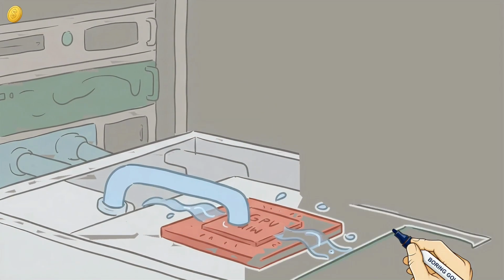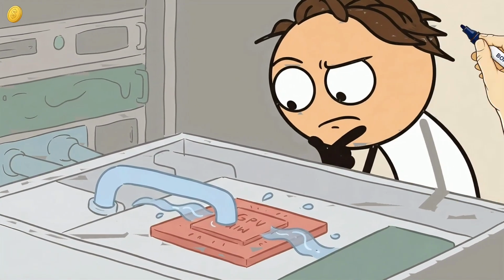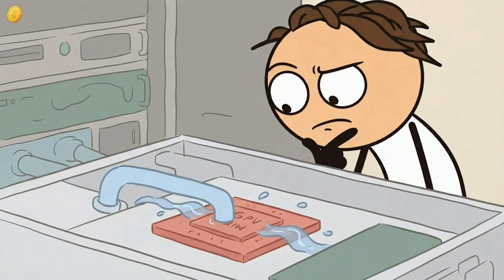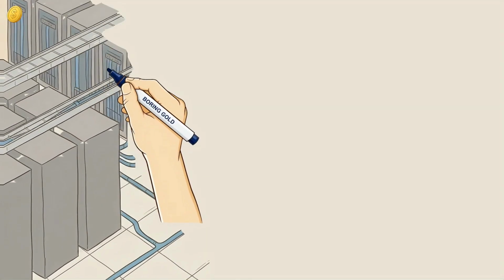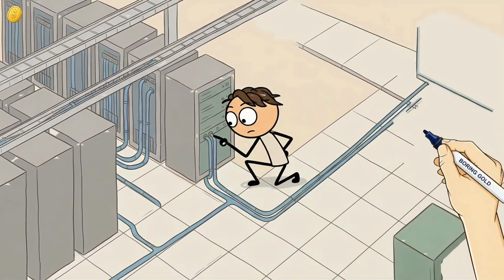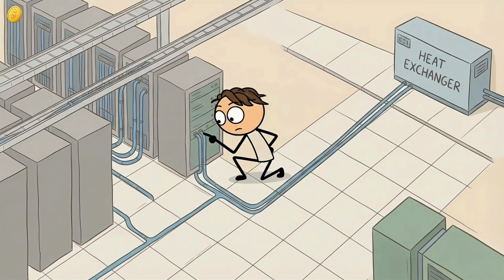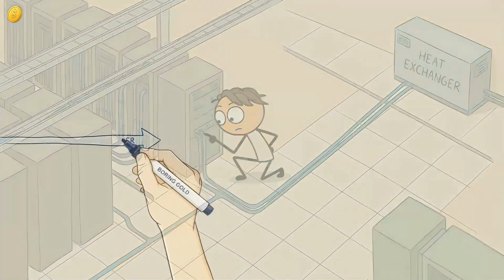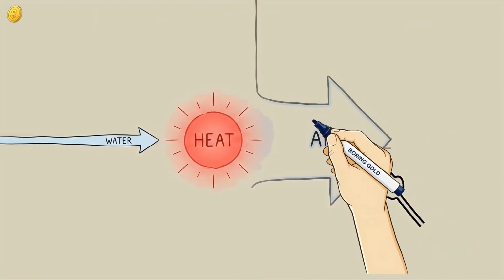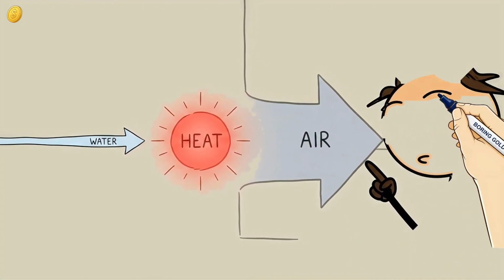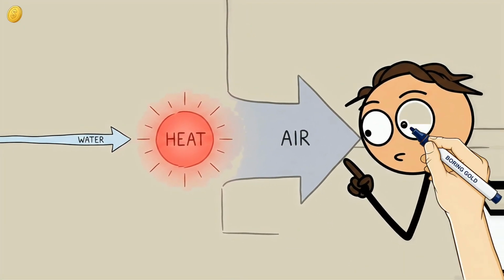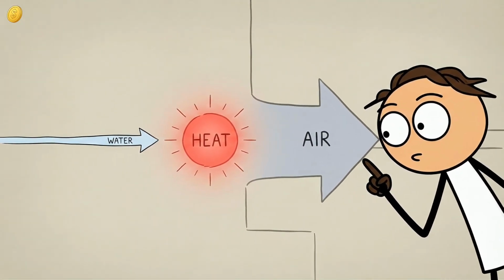Direct liquid cooling, or DLC, brings cooled water directly to the server chassis through cold plates attached to the surface of the GPU die. Water flows past the chip, absorbs the heat, and carries it away to a heat exchanger at the edge of the room. Because water carries 4 times more heat per unit mass than air, you can remove the same thermal load with far lower flow rates, far quieter systems, and far greater precision.